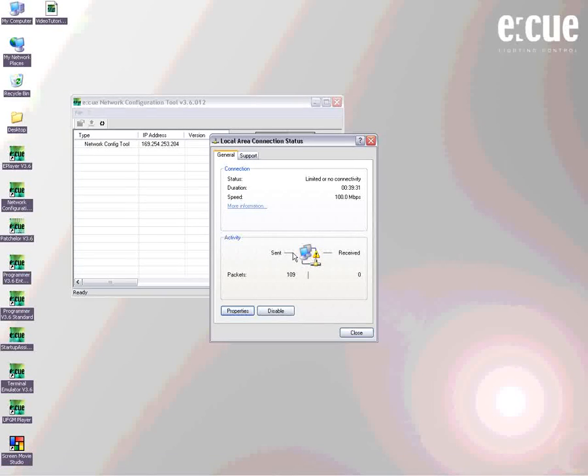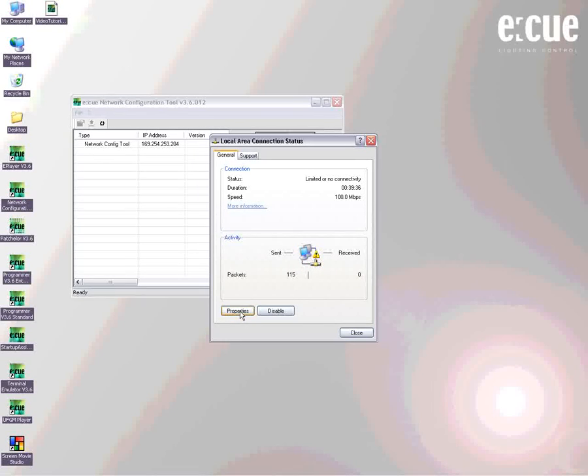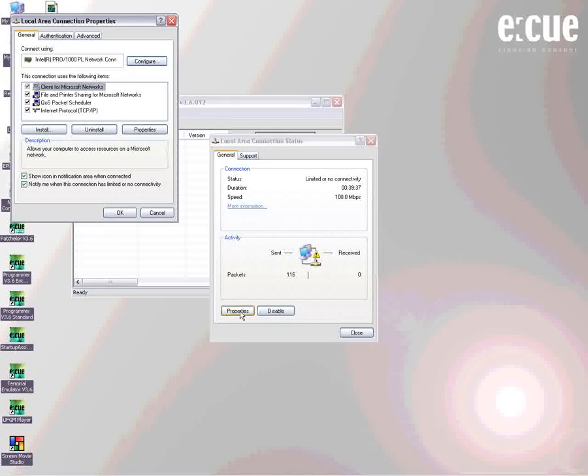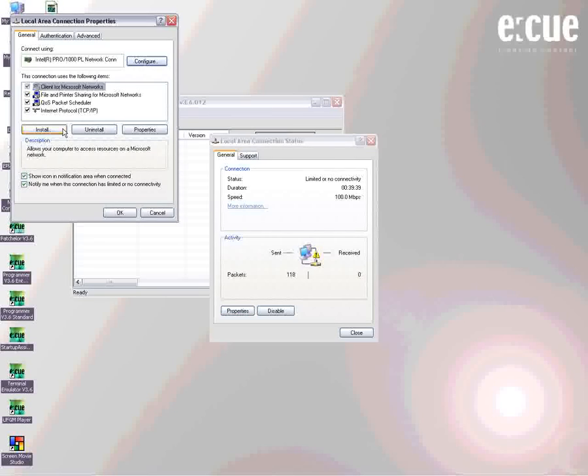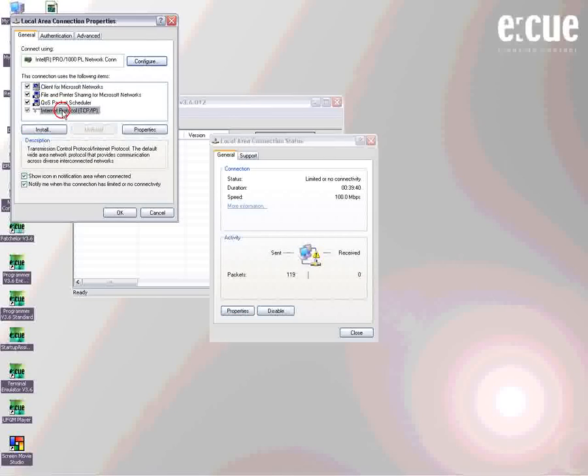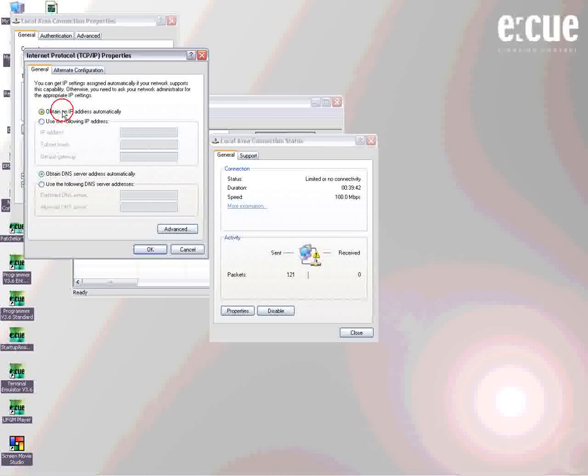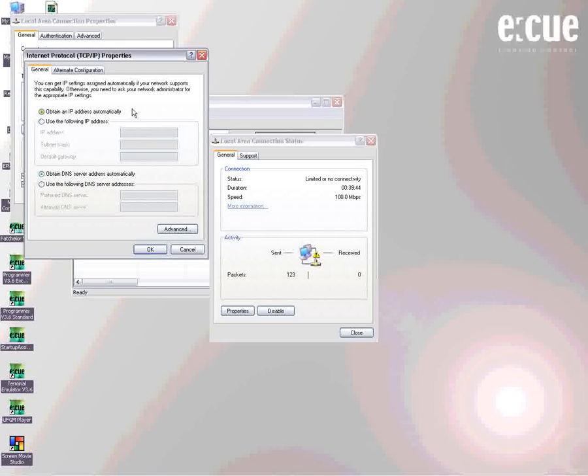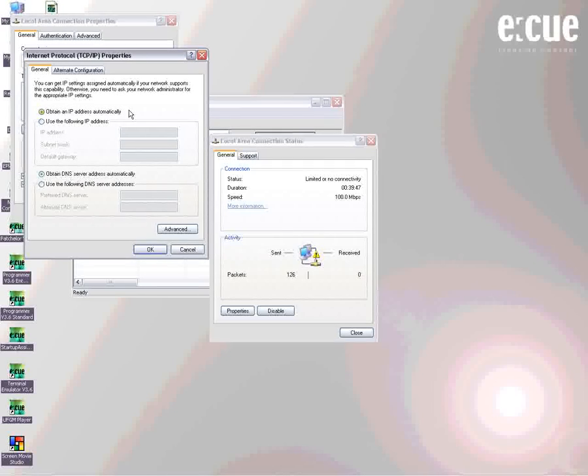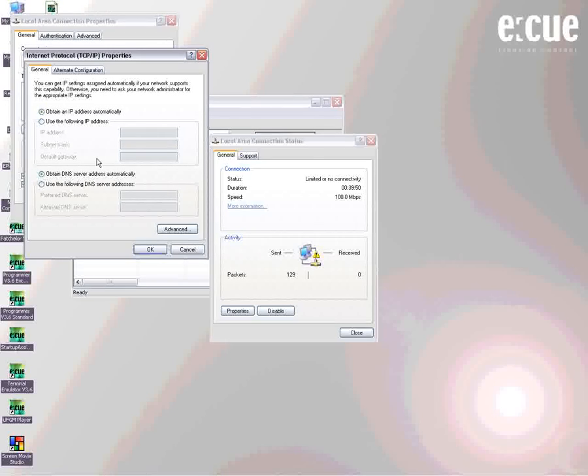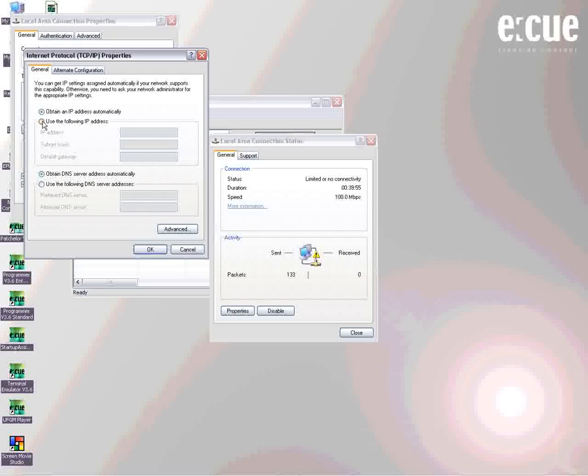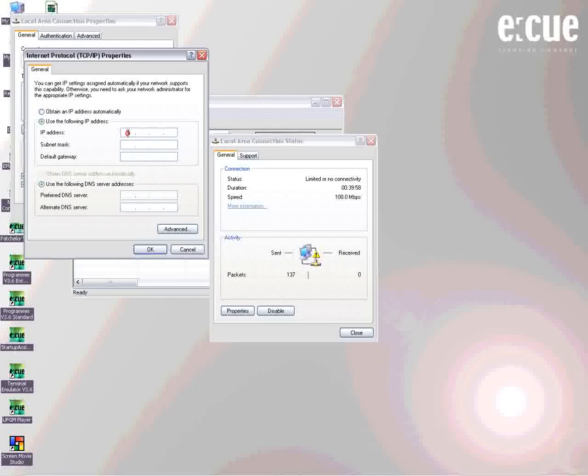Therefore, we open up the local area connection status and see that there is something wrong with the connection. What we have to do now is change the IP address of this computer by opening up the Internet Protocol TCP/IP and change it from obtaining an IP address automatically to use the following IP address. As all e:cue devices will come to you with a certain IP address, we have to change our computer to this address range in order to make it visible for the NCT.